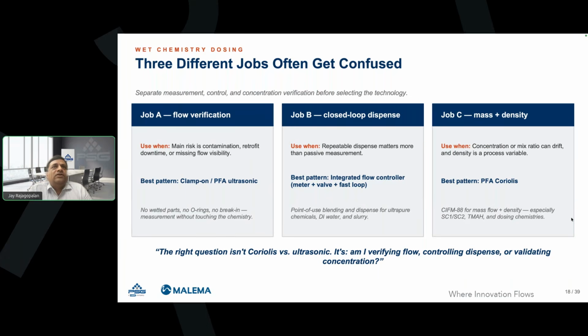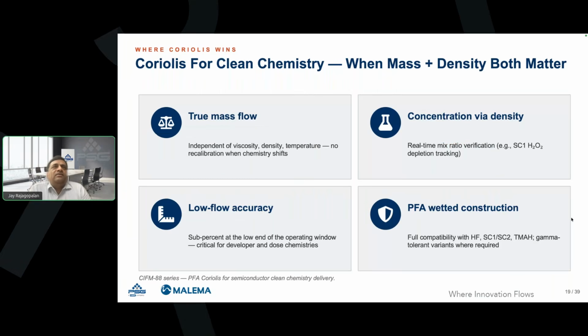Let's look at Coriolis, especially on the formulation side or blending side. Coriolis is the only technology in the flow measuring world that measures flow directly; mass flow is being measured. So mass is a conserved unit, unlike volumetric flow. So it is independent of changes in viscosity, density, or temperature. So if you're using it for one chemistry and you apply it to different chemistries, you don't need to recalibrate the devices.